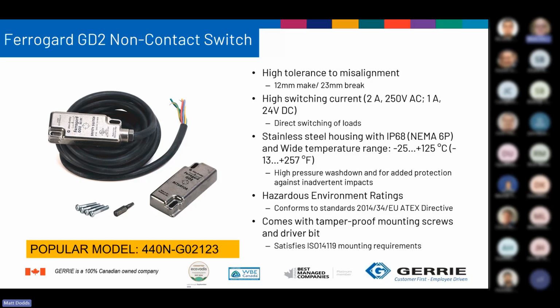In ISO 14119, it does talk about not only the use and application of the switches, but also the mounting. So again, popular model there, the 440N-G02123, which is, again, DC, two normally closed, one normally open for monitoring with a 3-meter cable.